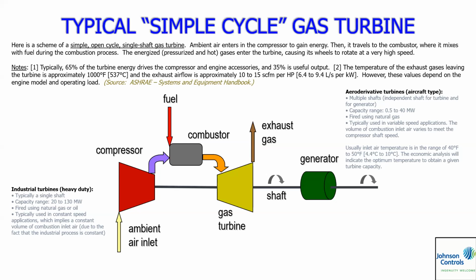So there's really two basic types of turbines that we see in the industry. There's industrial turbines, which we'll consider heavy duty. Those are typically a single shaft, and they get to be pretty big, up to 130 megawatts in power. And those are either natural gas or oil fired. Typically constant speed. What we normally see in the LNG world, like an LM6000 for my friends at Baker Hughes, are aeroderivative turbines, which are jet engines.